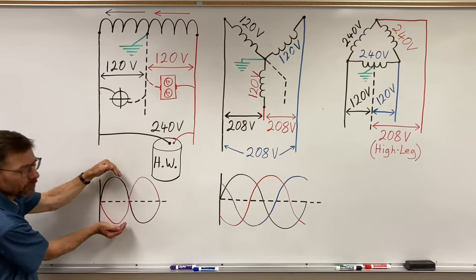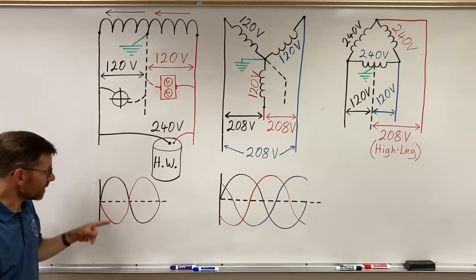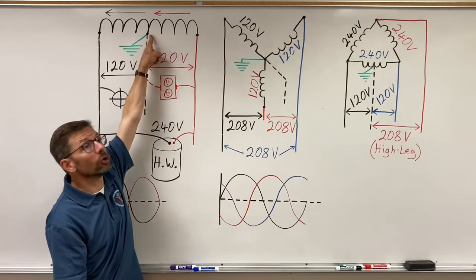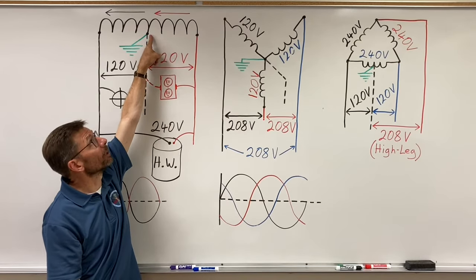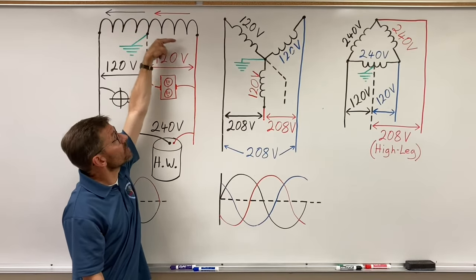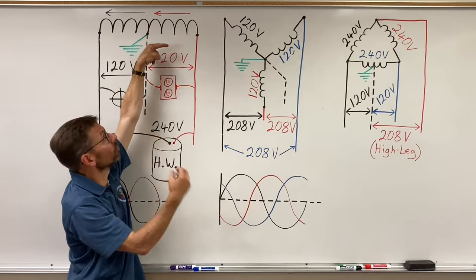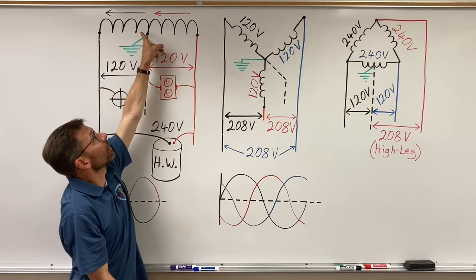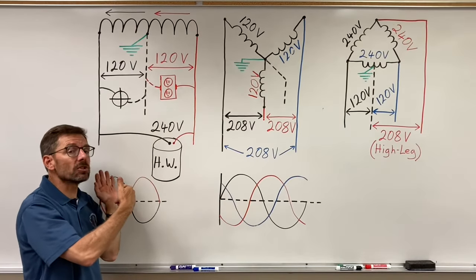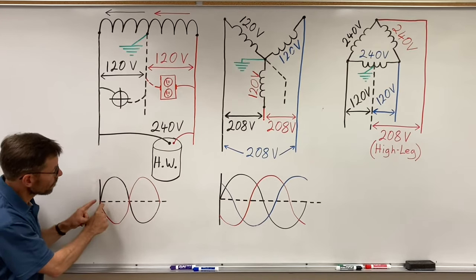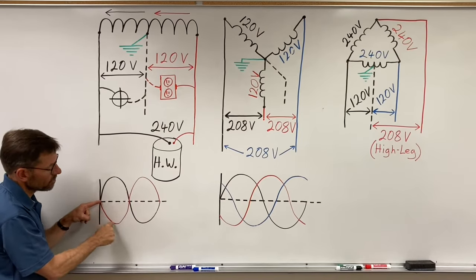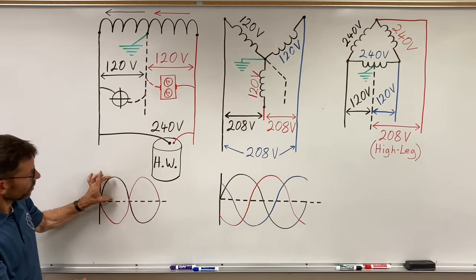Why do I point the sine waves in different directions — why aren't they both going the same way? Because I'm measuring relative to the neutral. From the neutral point of the transformer, looking toward the red wire, the voltage is pushing toward me, so I'm looking up voltage. Looking toward the black wire, I'm looking down voltage. So one appears positive and one appears negative at any moment in time — the black appears positive, the red appears negative.